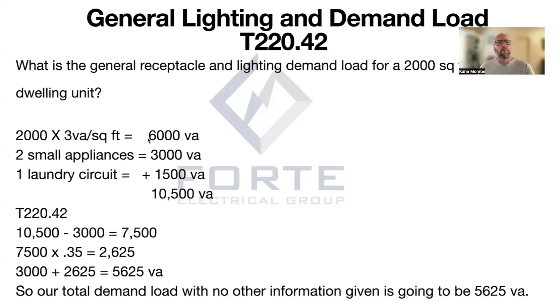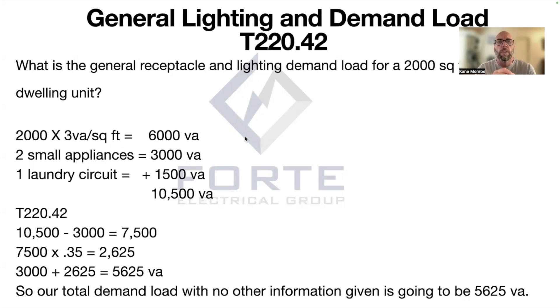Then don't forget we need to add two small appliance circuits, which is another 3,000 VA, and then we have to add one laundry circuit, which is 1,500 VA. So we get a grand total of 10,500 VA when we add all of this up.